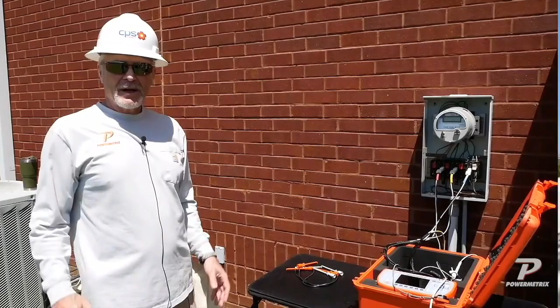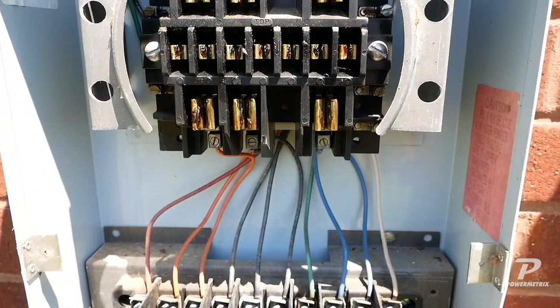Okay, this is great training right here, because this is field testing at its best. So remember, we have said this is a corrosive environment where we are. Keeping that in mind with the corrosion, here's what we did. We sprayed down, and all of you saw the before and after pictures behind the meter back here on the stabs and on that test switch. So we sprayed it down really, really well.